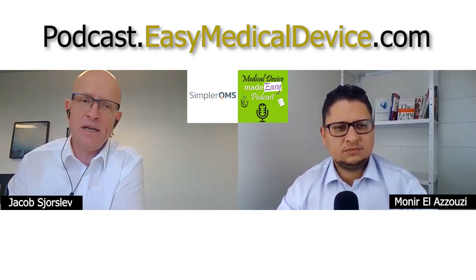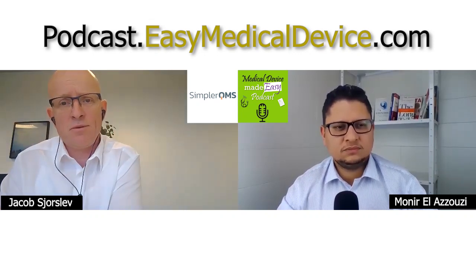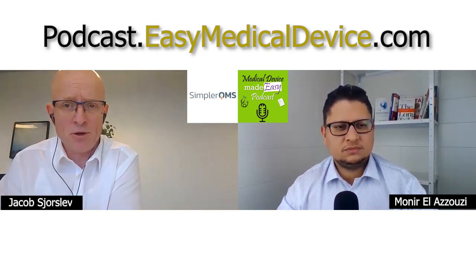You go into OQ and PQ, where you have an approved test protocol that totally specifies what you are testing, what the expected outcomes of the testing are, and you have a template for capturing the results. And here it's important that you do the testing in a real environment that is alike what will be used when we go into production.